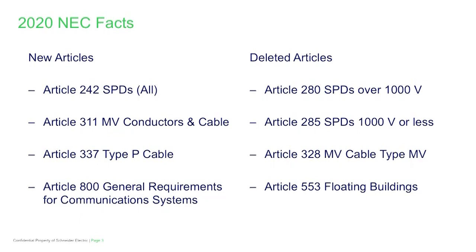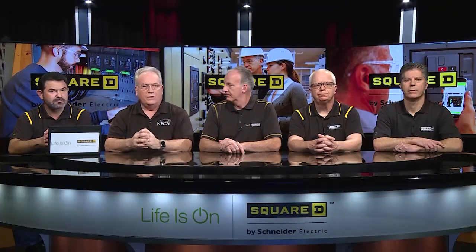The next new article is Article 311, and it deals with medium voltage conductors and cables. This resulted from removing all of the medium and high voltage provisions in Article 310 and relocating them into a new Article 311.